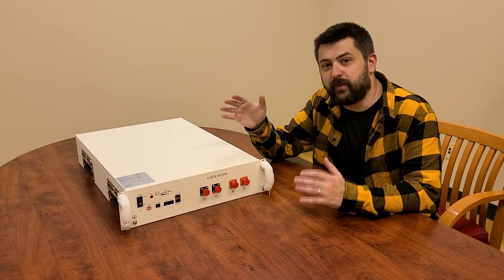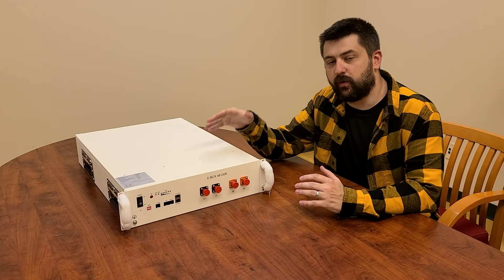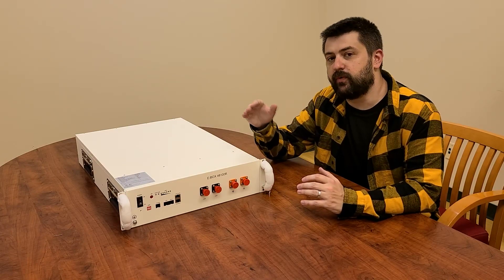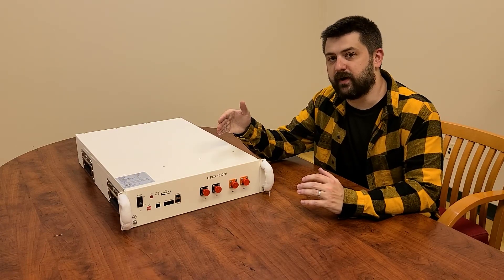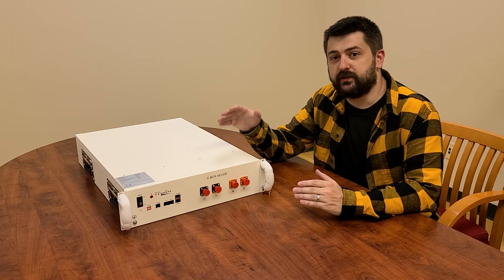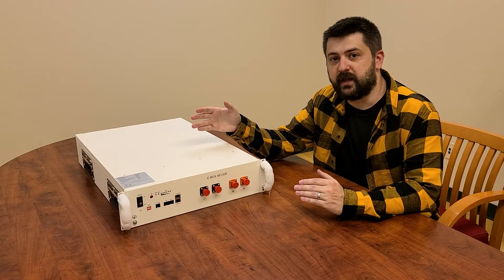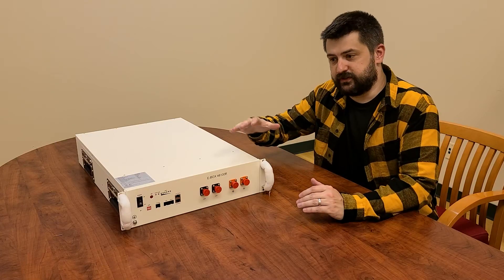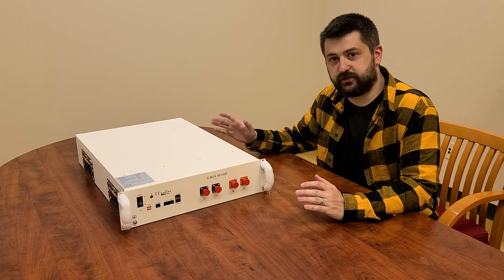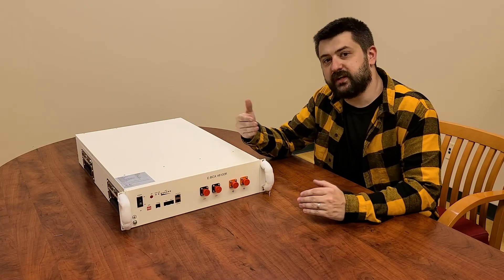So here it is, the Pytes E-Box 48100R. This unit is going to give you 5.12 kilowatt hours of power — that's 51.2 volts at 100 amp hours. The other fantastic thing about this battery is that it's UL 1973 rated, which is fantastic for the North American market. I'm going to go through the front of the unit as well as the general construction, some of their design choices, and also open up and look at all the internal components. So stay tuned for that.